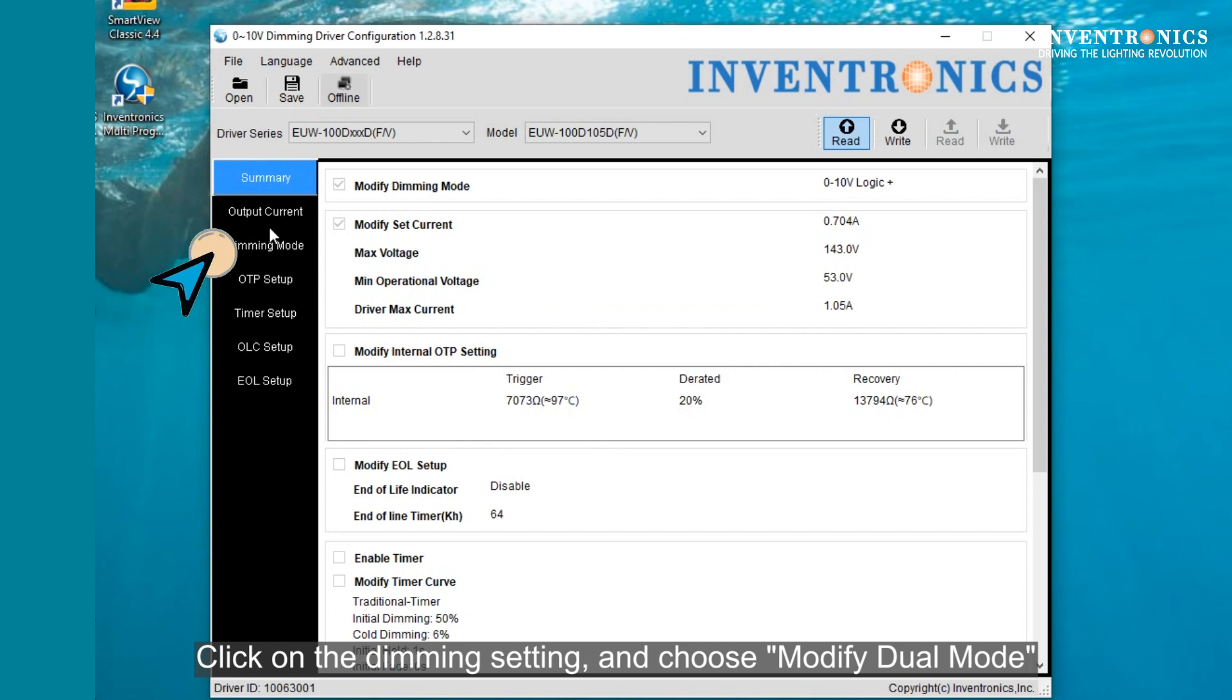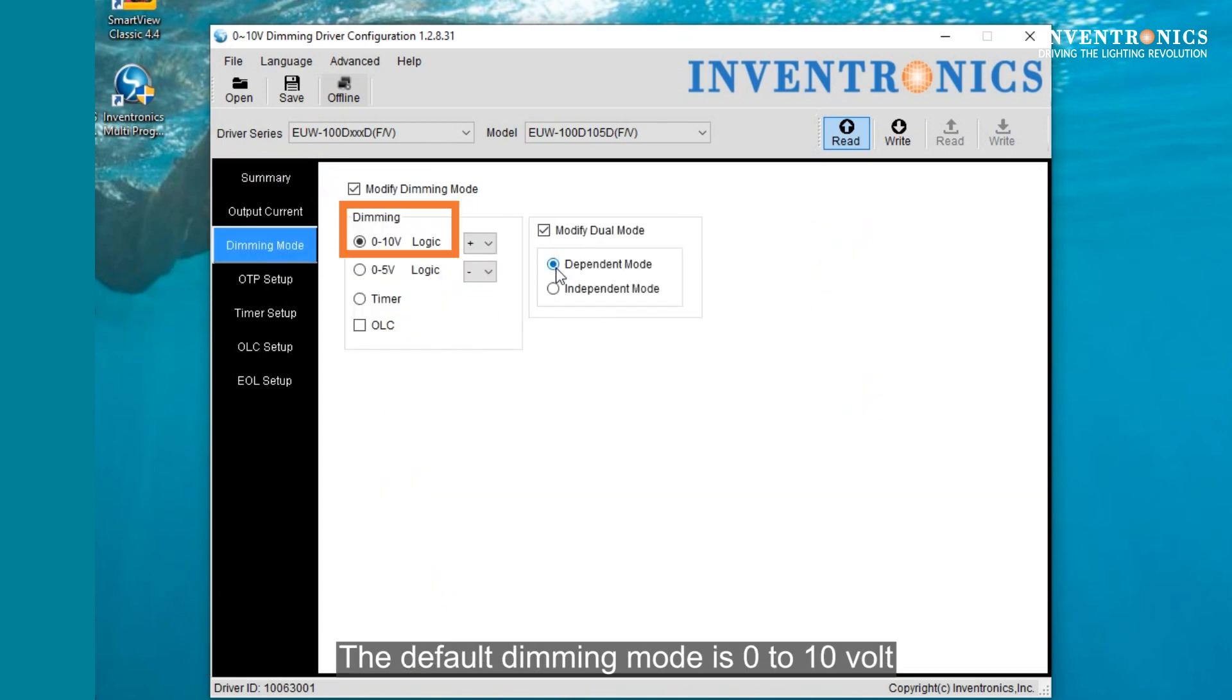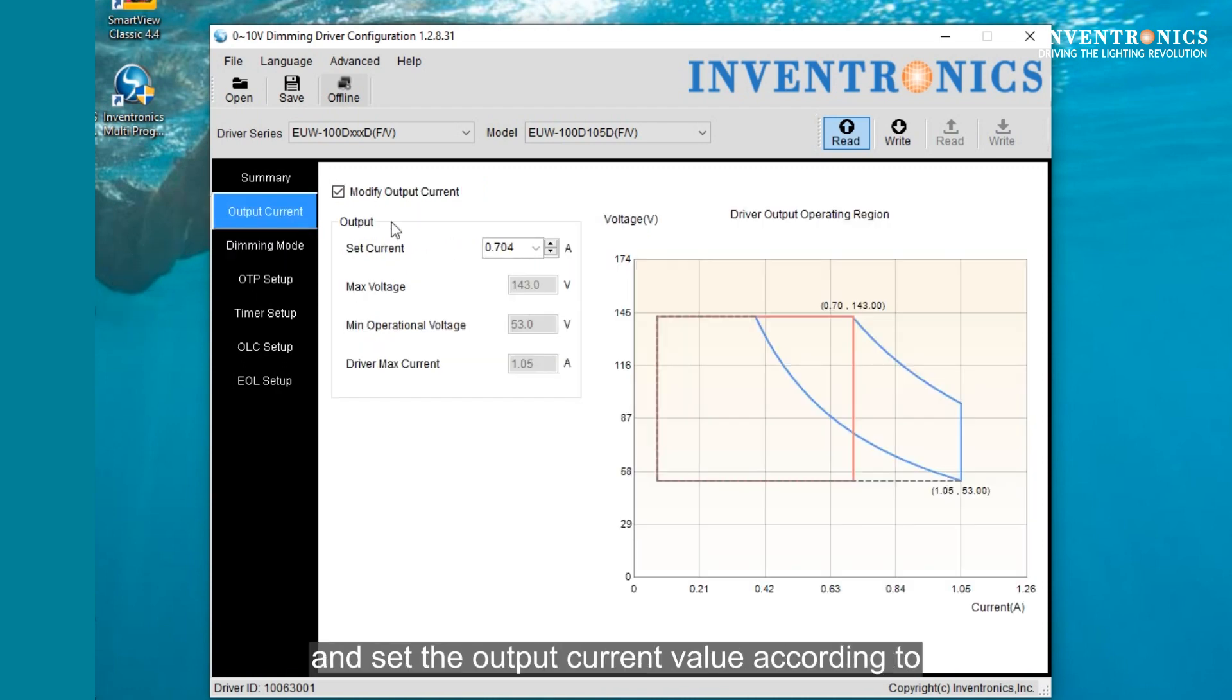Then click on the Dimming setting and choose Modify Dual Mode. The default dimming mode is 0 to 10 volt. Then, you will click on the Output Current setting and set the current output value according to the expected power of the luminaire.